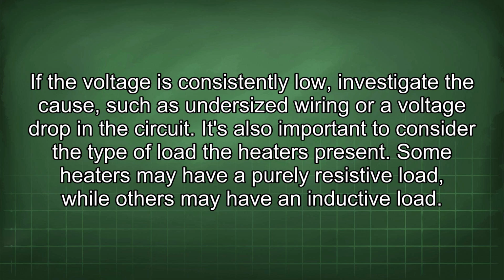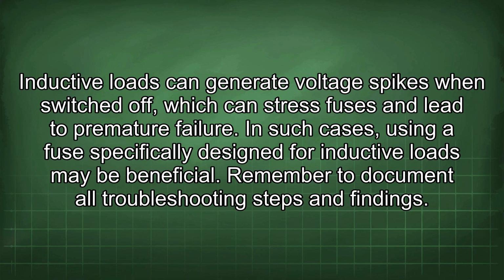It's also important to consider the type of load the heater presents. Some heaters may have a purely resistive load, while others may have an inductive load. Inductive loads can generate voltage spikes when switched off, which can stress fuses and lead to premature failure. In such cases, using a fuse specifically designed for inductive loads may be beneficial.